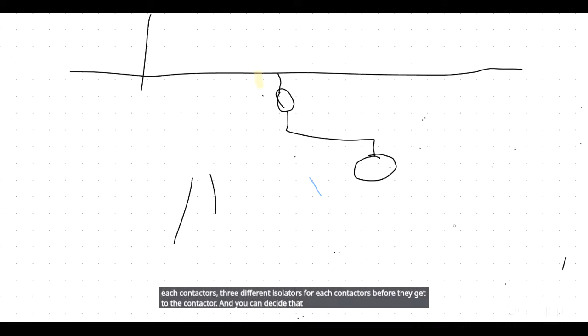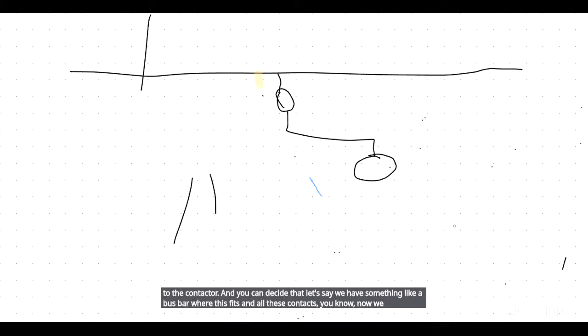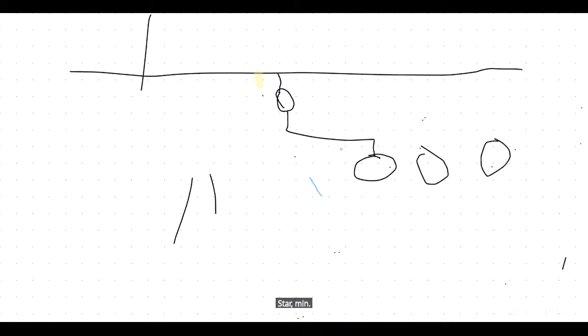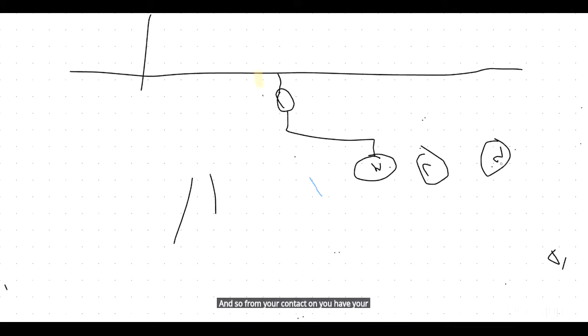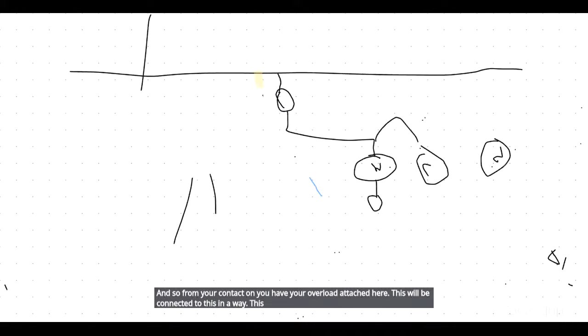And you can decide that, let's say we have something like a bus bar where this fits and all these contactors connect. Now we have three contactors: star, main, delta. And so from your contactor now, you have your overload attached here. This will be connected to this in a way, this two comes down, this comes down.